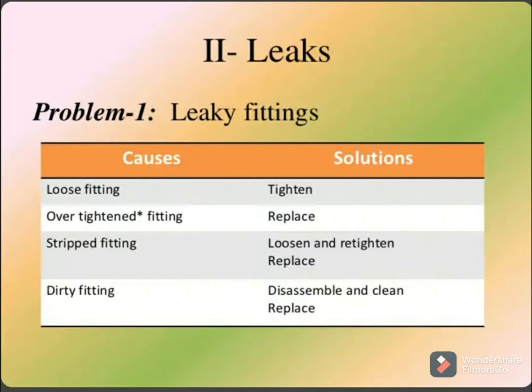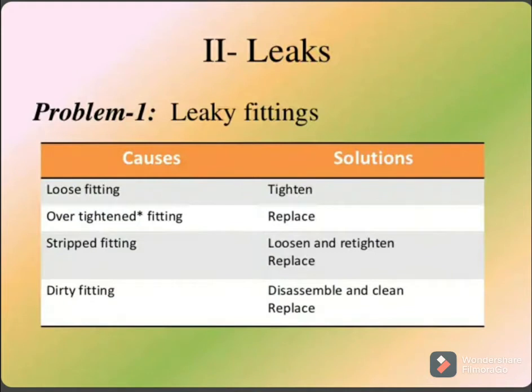Next is the second point, the leaks. What is the problem coming? Leaking fitting, loose fitting, that is the cause. What is the solution? Tighten the fitting. Over-tightened fitting: replace. Stripped fitting: loosen and retighten, or replace. Dirty fitting: disassemble and clean, or replace. That is the leaks problem which we are facing in our troubleshooting when we are operating our HPLC system.